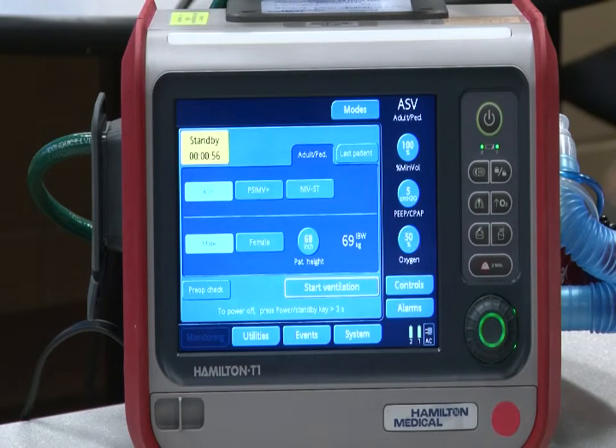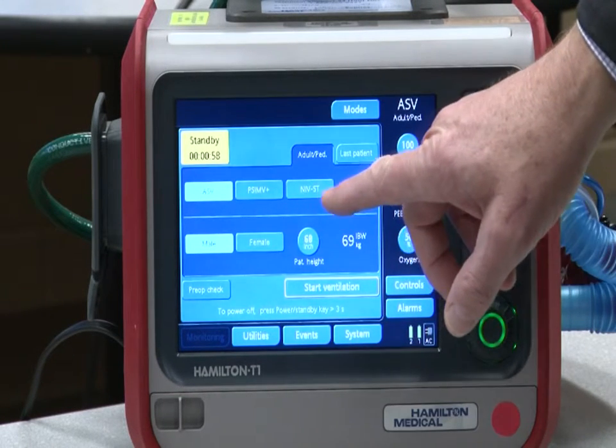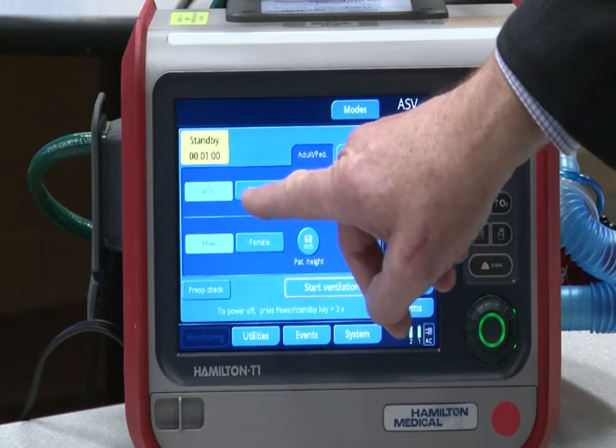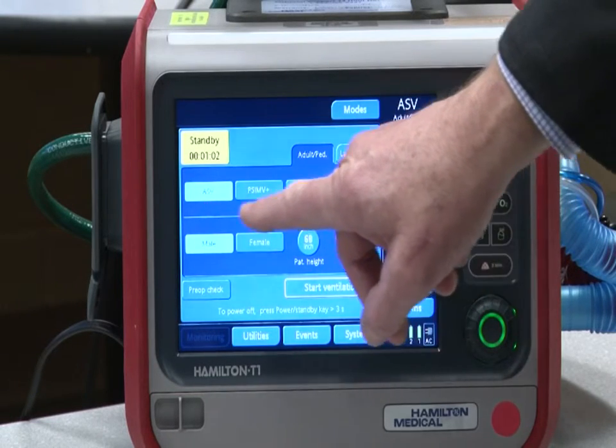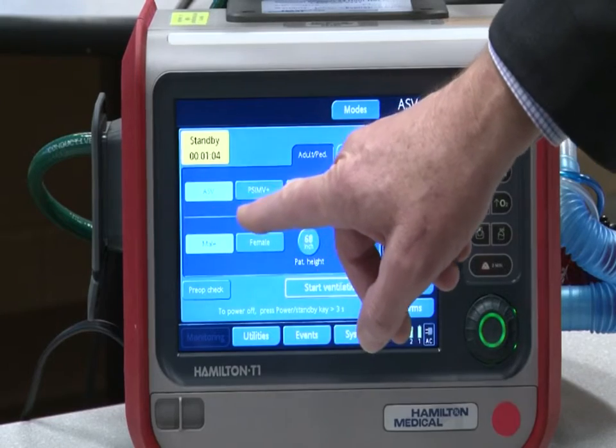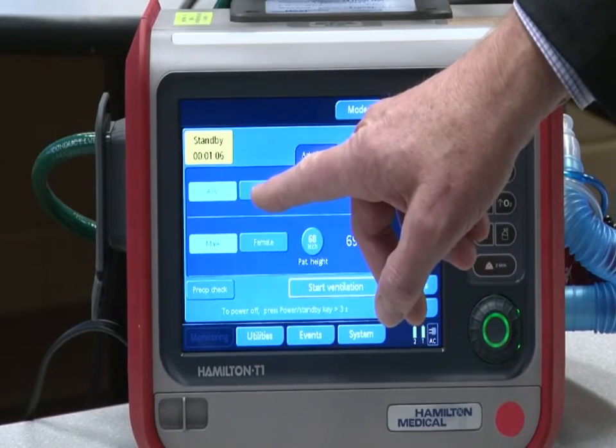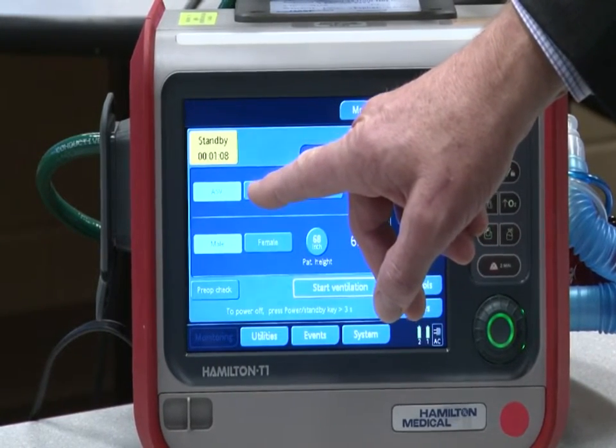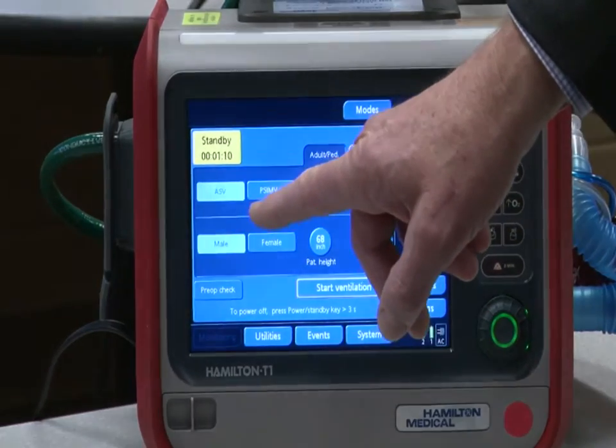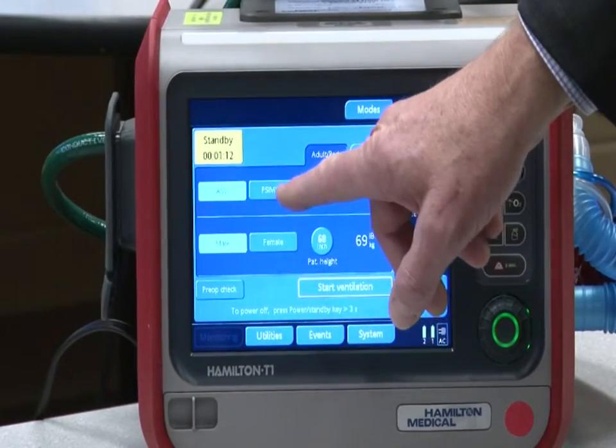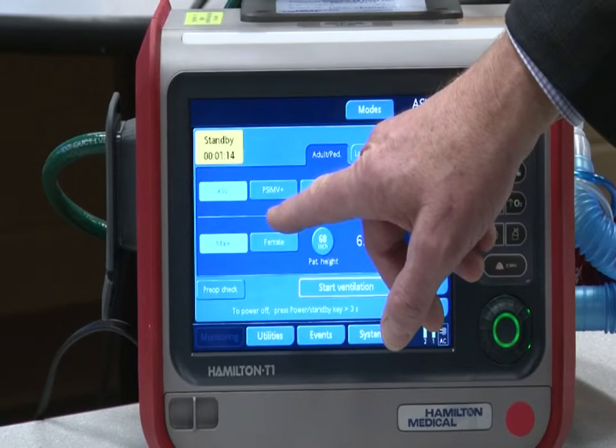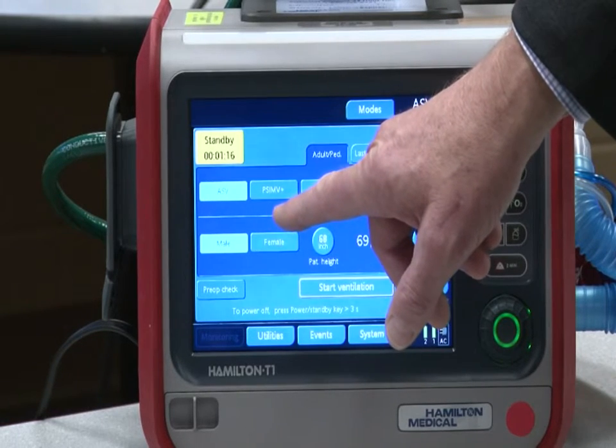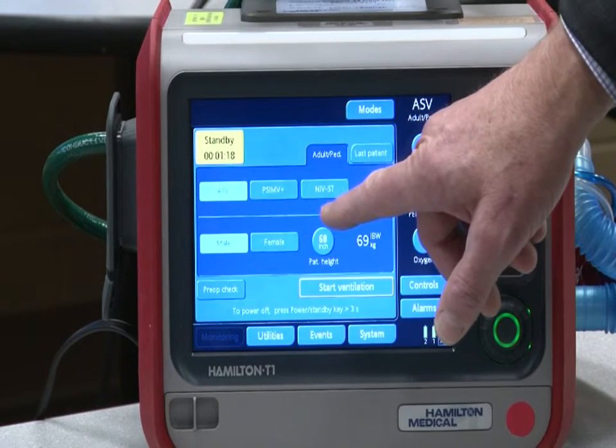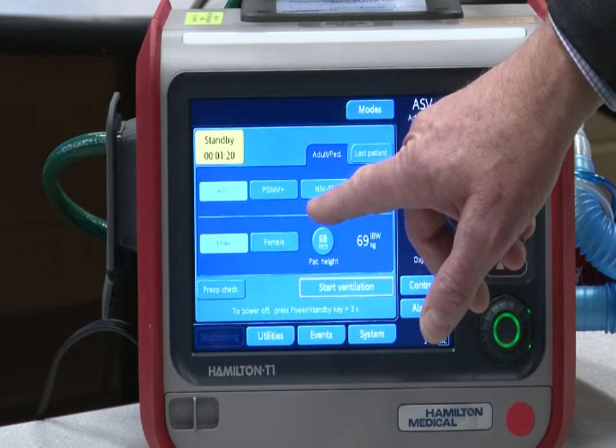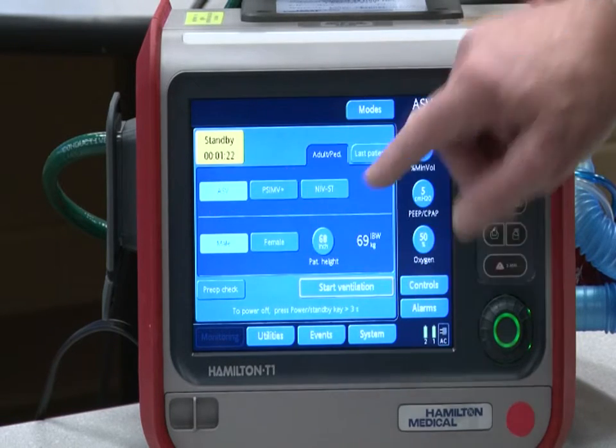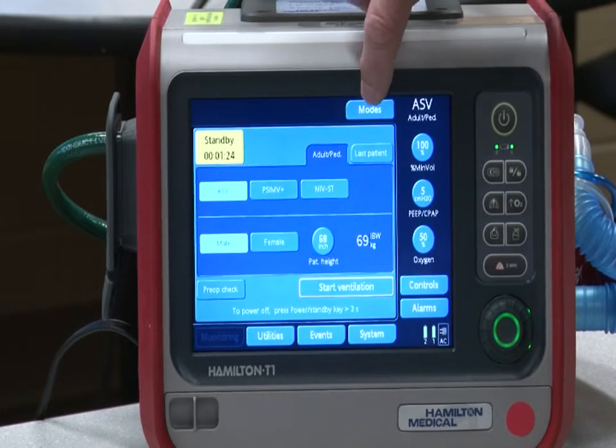Okay, so we see some different things on the ventilator here. These are the three primary modes that you're going to be using. ASV, and your ventilator, as did mine, came up automatically into ASV because that's the mode that we're going to use 90% of the time, if you will. Plan B is going to be this middle one, which is called PSIMV+. We'll talk more about that. And then when you're doing non-invasive, it's going to be NIVST. So those modes are the same as the modes that are available up here under the modes key.